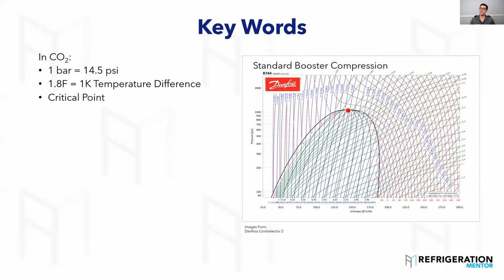So on this right hand, this is from Danfoss Cool Selector 2. If you don't have this software, I highly recommend downloading it. It takes a little bit to learn, but there's so much great information in there on Danfoss products. But right at the top of the curve there, that's the critical point. Every refrigerant has a critical point. Okay. We just don't see it with HFCs or HFOs or CFCs back in the day, because we never got to that critical point, critical temperature or critical pressure, because it was so high.